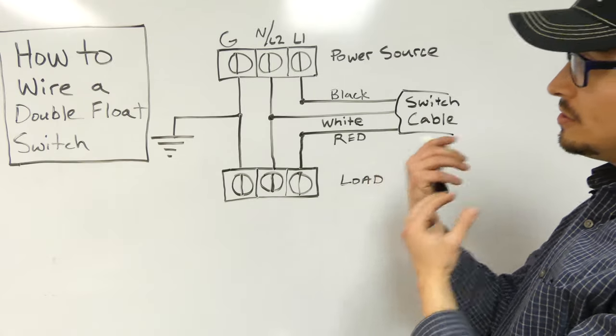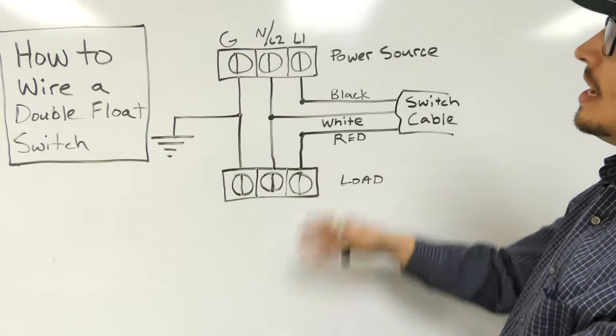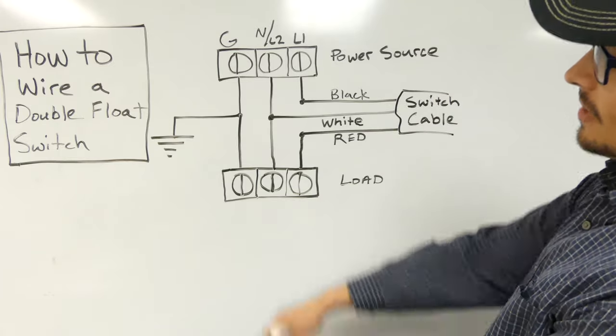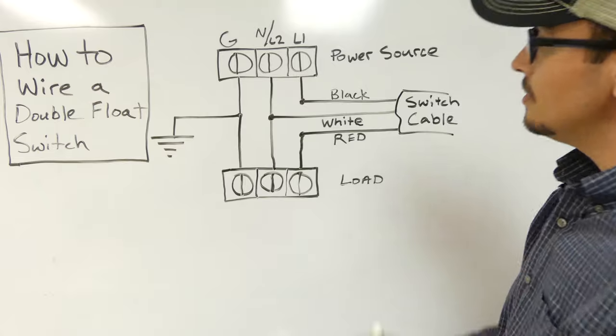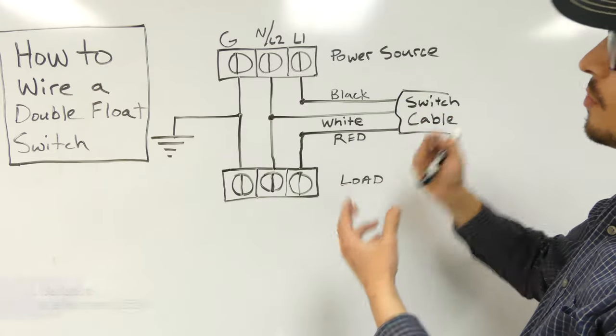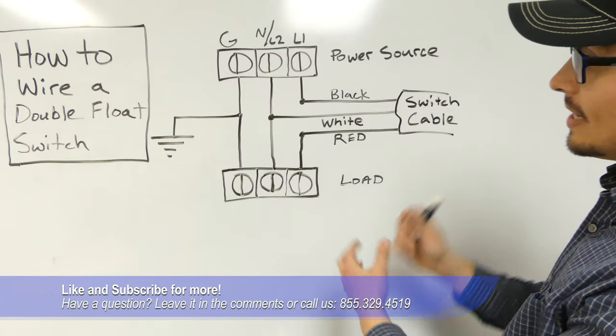And that's what we're accomplishing with the relay and holding circuit that's created when both floats come up. And then that holding circuit doesn't break connection or lose power until that bottom float falls back down, which is what gives us that wider range of pumping. So hopefully this quick demonstration showed you simply where your wires go when you're trying to wire a double float switch.